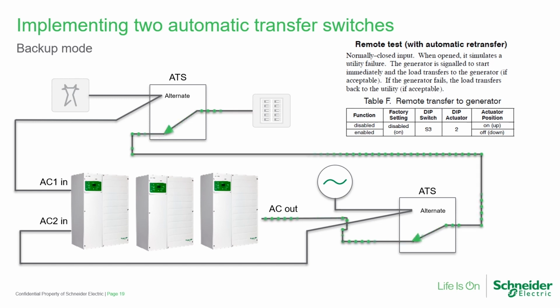Since the remote test terminals TB71, TB72 are always open, a utility failure is always simulated, so the alternate would always be supplying power, except if the alternate fails, in this case utility, and then the load transfers to the inverters. If the batteries get low, the aux port can be used to open the normally closed connection across TB71, TB72. In this scenario, the Series 185 auto transfer switch will control the generator. Once the desired charge is reached, the aux port will deactivate and close the relay, causing the load to be transferred to the inverter with zero delay, provided S3 position 1 dip switch is off, which means the transfer bypass to the utility delay is disabled. Generator will continue to run for 2 minutes to cool down.